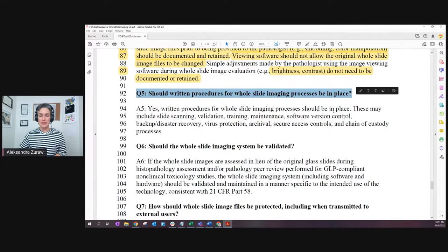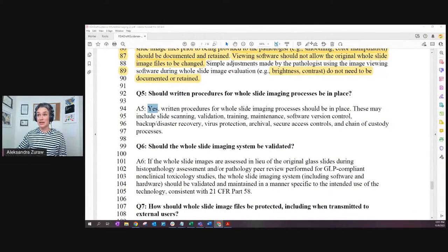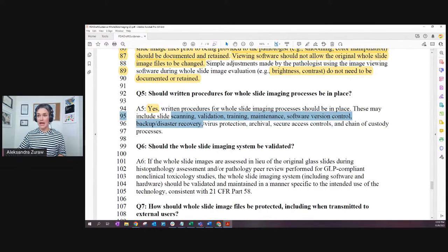Question five: should written procedures for the whole slide imaging process be in place? Yes. In GLP, you need written procedures for anything. The more I work in GLP, the more I realize it. In GLP there's even a format mandated for how you sign things, how you put in the date, how you correct input data - written procedures for everything. Obviously it's a big deal that you can now look at slides on a monitor instead of under the microscope. So yes, there should be written procedures. FDA says yes - they may include scanning, validation, training, maintenance, software version control, backup, disaster recovery - everything.